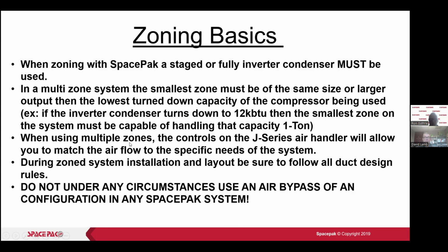When using multiple zones, the controls on the J series air handler will allow you to match the airflow. You can run it by pressure, or you can just run it at a lower percentage of speed to account for running 1 zone versus 2 zones. All right, so you just have to be careful about how you lay out those zones.